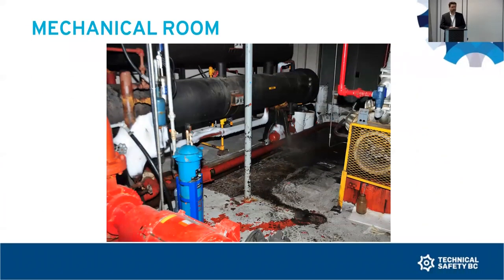This picture really shows what the responders and investigators first encountered in the mechanical room at the Fernie Memorial Arena. What you can see here, it's a very busy picture. This is a brine system line, and there's an opened coupling here. Now, there's a lot of this black substance on the floor, which is some of the oil and brine residue that came out of that pipe. You can see here as well some evidence of spray coming out of that pipe.